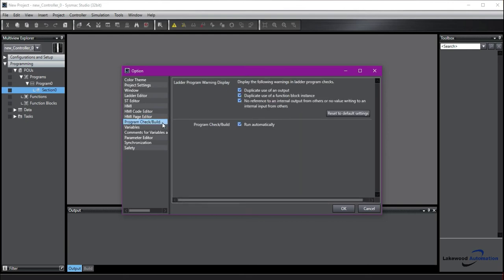Program Check Build. We recommend that you keep all of these checked. It's going to allow Sysmac Studio to automatically look for the duplicate use of an output, duplicate use of a function block. This can be helpful because sometimes you make these errors and you don't realize it, and it can be challenging to figure out what's wrong in your code.